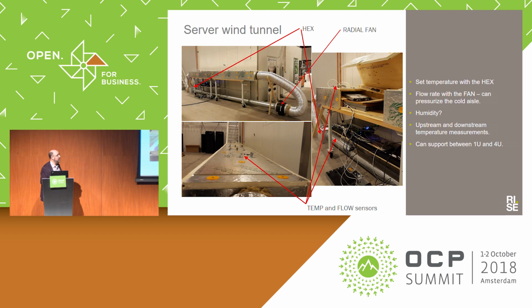To do that, we use this wind tunnel. It now has cladding on it, but you can see a long pipe along the bottom, with a radial fan that accelerates air down the pipe to a heat exchanger at the end, where a water loop lets us control the inlet temperature. The long pipe lets us accurately measure the airflow, the volumetric or mass flow rate of air into the server.